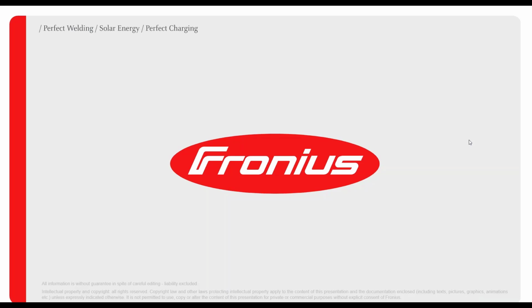It's way better for our system to have a smaller Fronius than a Multiplus or Quattro. The rule doesn't mean they have to be equal at all times - it means the Fronius has to be smaller than the Multiplus at all times. It's far better for system stability if the Multiplus is much larger than the Fronius, but if they're one-to-one, that's supported and fine.